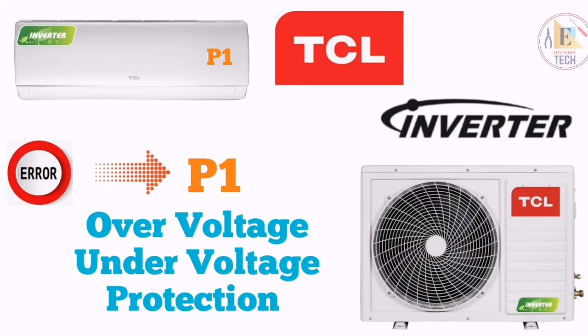When you see error P1, it means over voltage or under voltage protection. First of all, you have to check the main power supply of your unit. If the voltage is between 160 volt to 260 volt AC, then you have to check the voltage between line and neutral in your outdoor unit. In that also, if you get 160 to 260 volt AC, it means the voltage coming from your main supply is normal. And if the voltage is abnormal, then you have to check your main breaker and your main supply. And if the voltage is abnormal in your outdoor unit, then you have to replace your PCB and your unit will be in working condition.